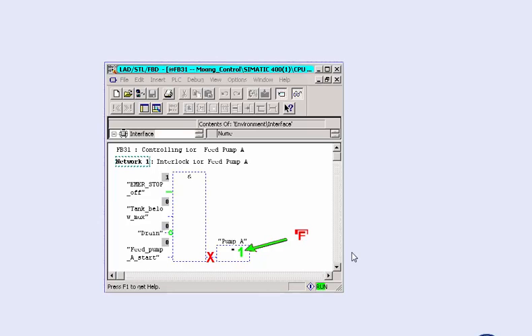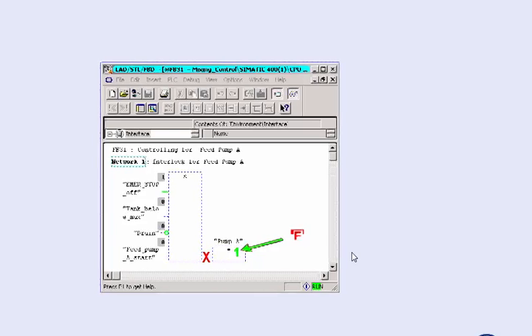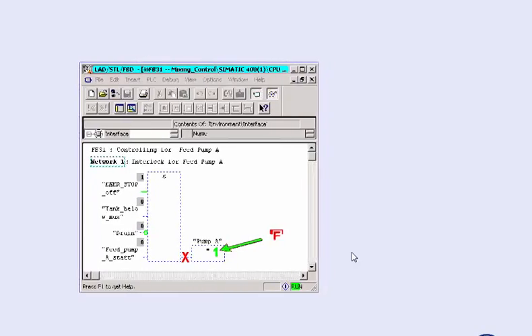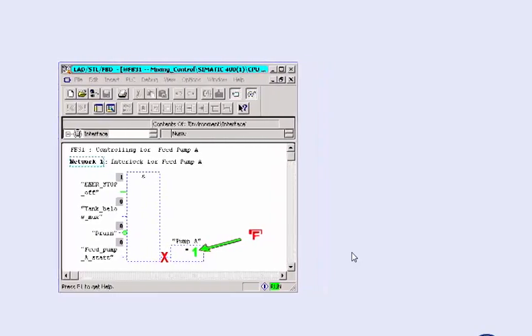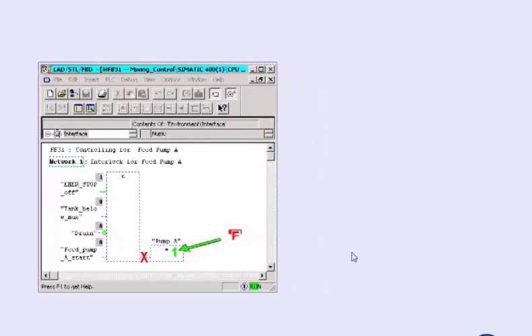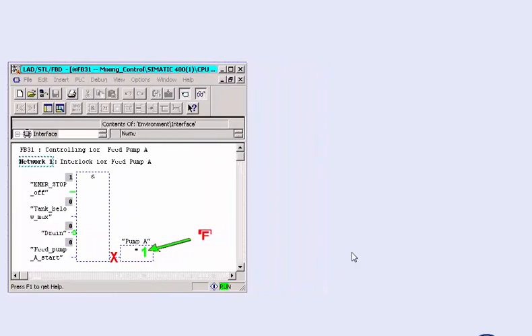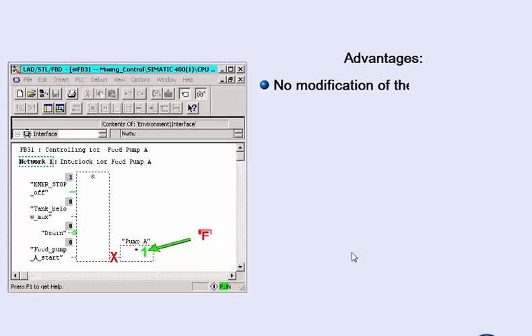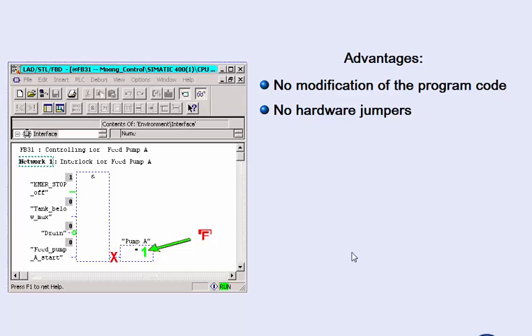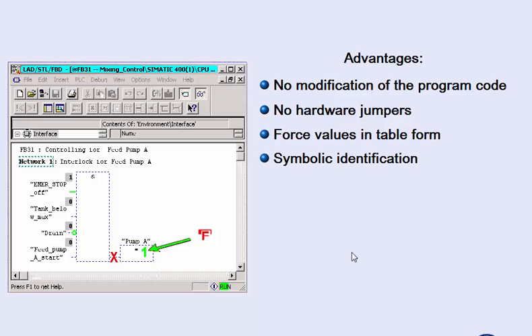This, as opposed to modifying with variable tables, enables you to define signal or variable values independently of the program sequence. The resulting advantages are the program code does not need to be changed, no hardware jumpers in the wiring are necessary, the forced values are stored in a table and are therefore comprehensible, and the forced values are marked in the program status with a symbol.